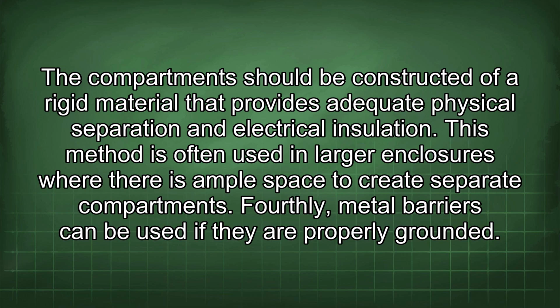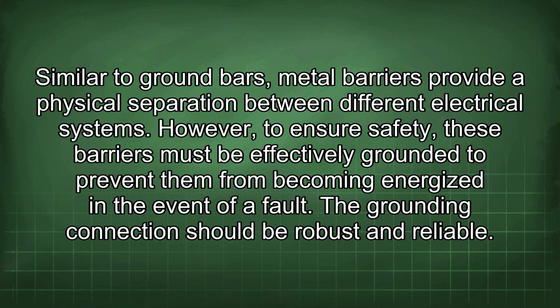Fourthly, metal barriers can be used if they are properly grounded. Similar to ground bars, metal barriers provide a physical separation between different electrical systems. However, to ensure safety, these barriers must be effectively grounded to prevent them from becoming energized in the event of a fault. The grounding connection should be robust and reliable.